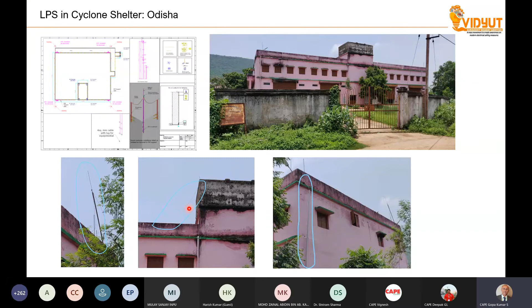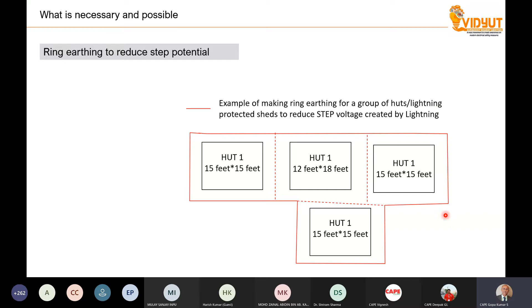Now I will try to cut it short. What exactly is required for protecting rural places? The most important is step potential. In order to avoid step potential, the conductor which is buried in the soil shall be buried across or around the building as a ring conductor. A ring conductor limits the potential difference, and this is much better. The best way of protection is a container, but of course, a container is very expensive. You cannot put containers at several places and ask people to sit inside them during a lightning strike.